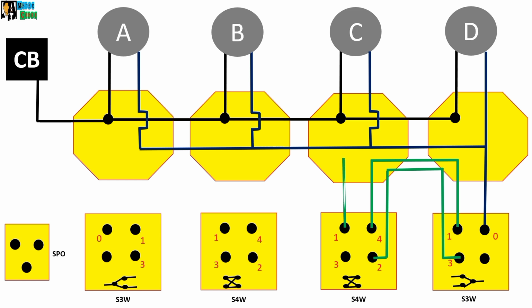And the traveler terminal 1 of the 4-way switch is connected to terminal number 4 of another 4-way switch. Terminal number 3 of that 4-way switch is connected to terminal number 2 of the other 4-way switch. And terminal number 1 of the second 4-way switch is connected to...